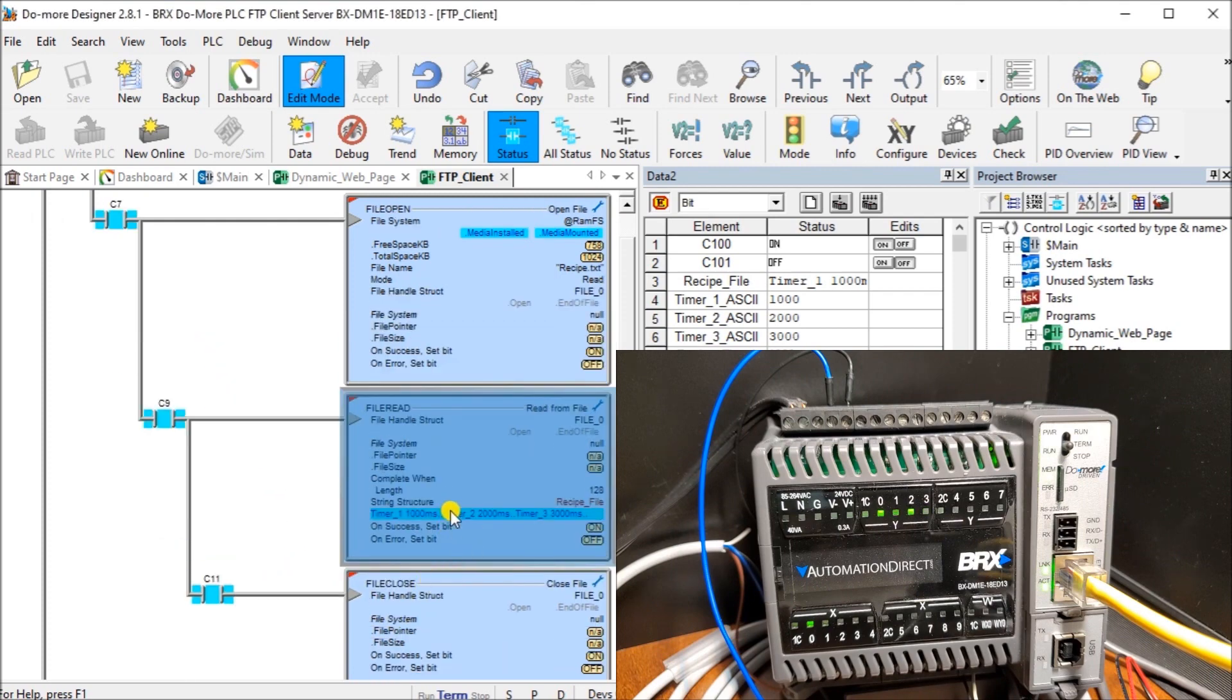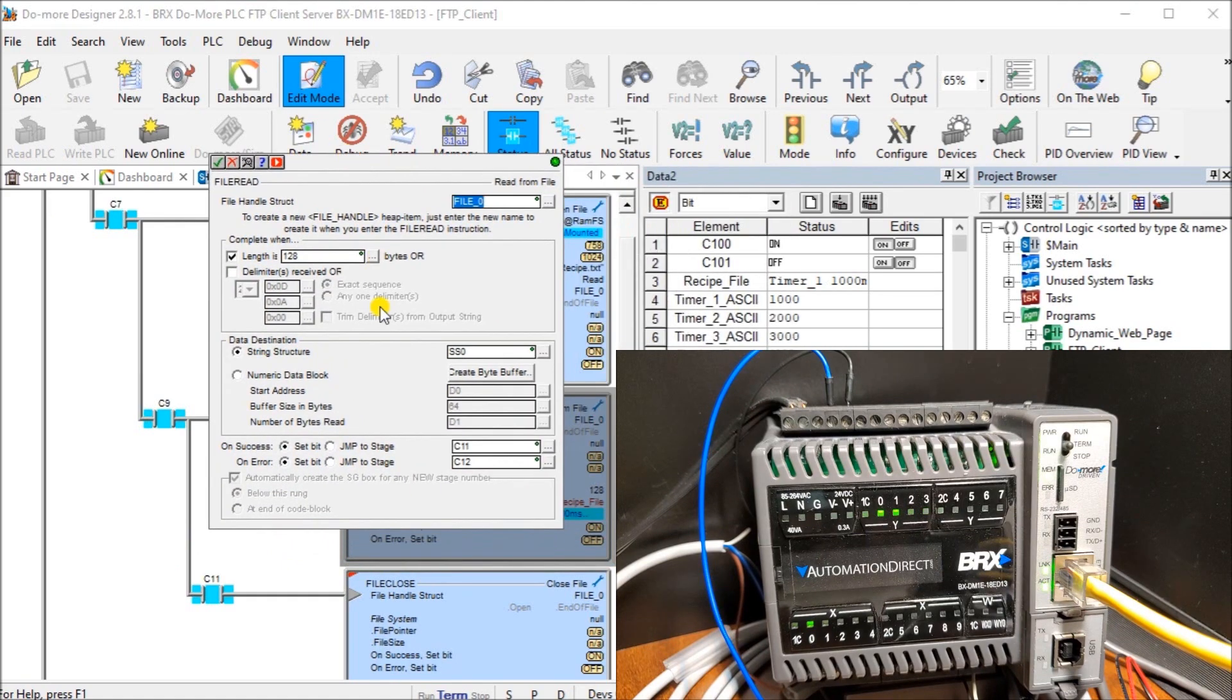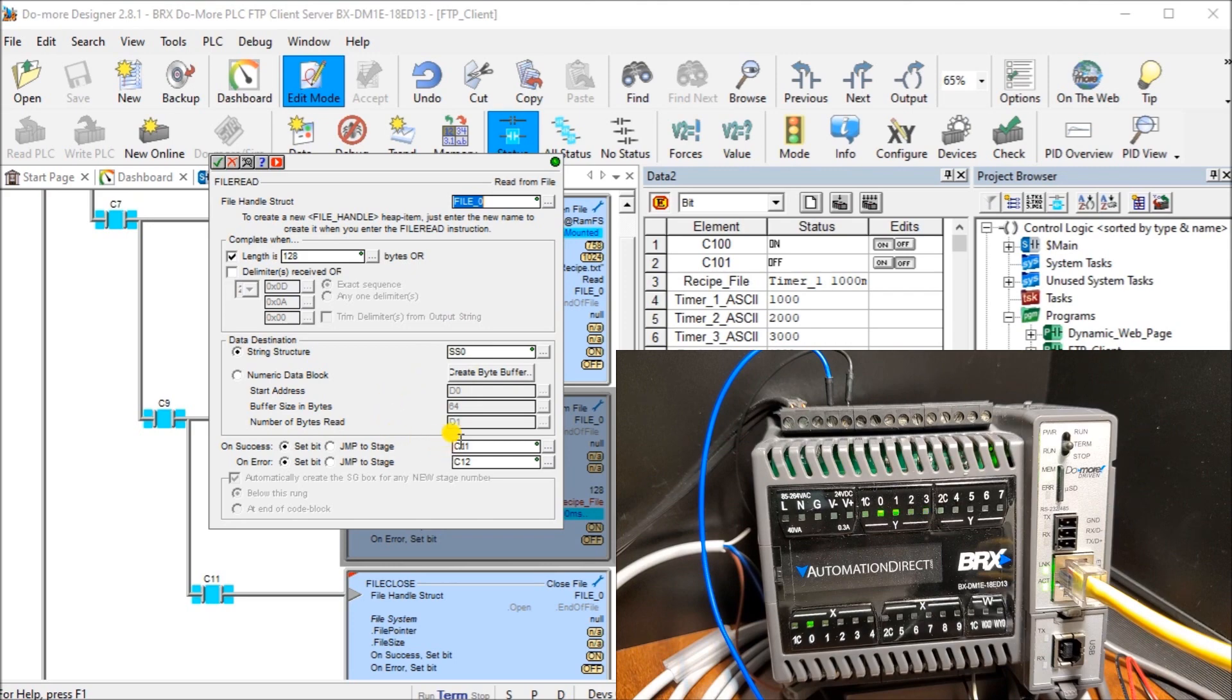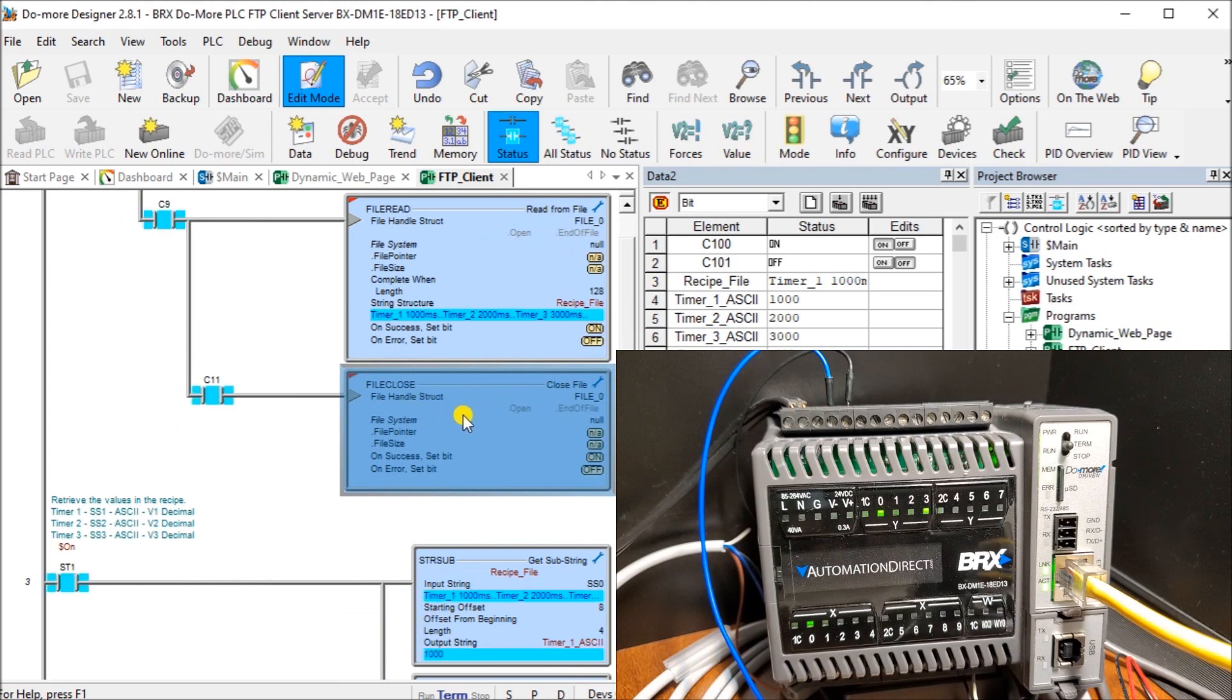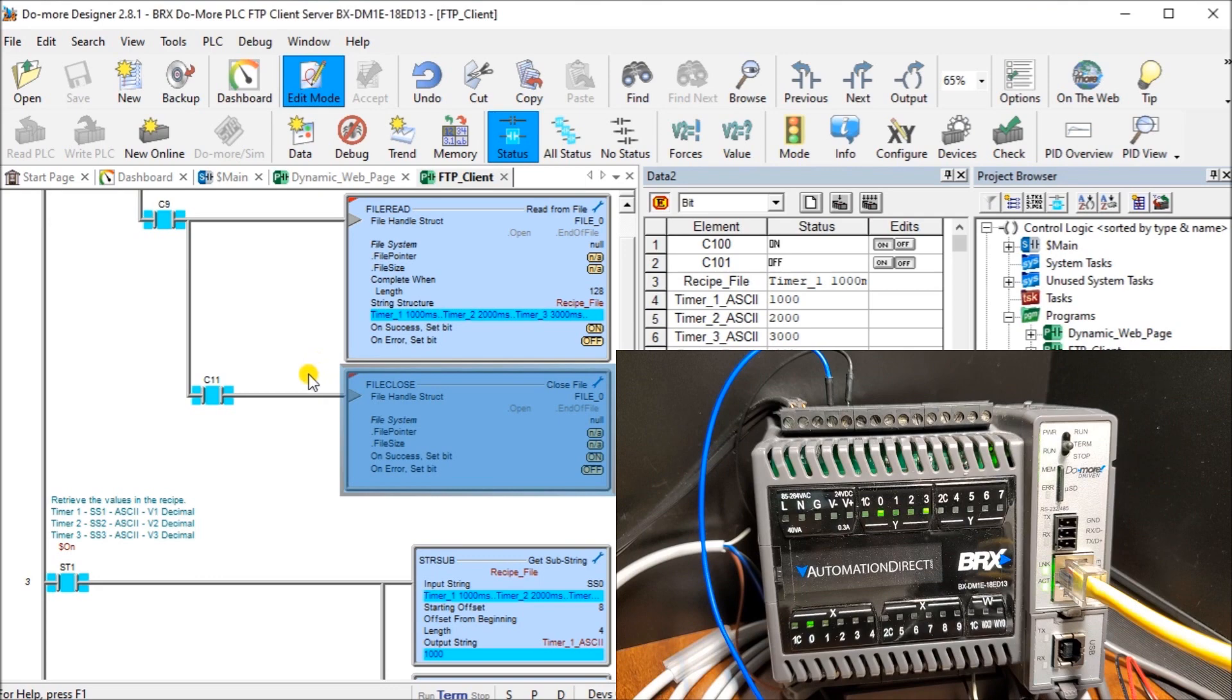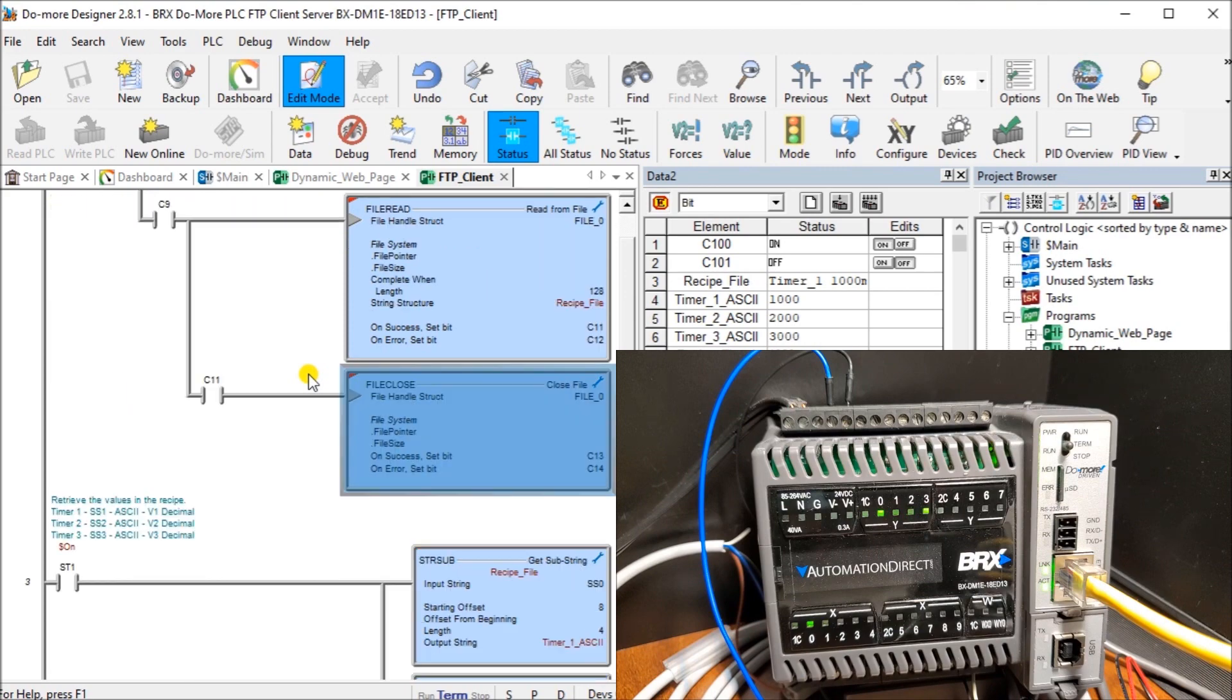Once C9 comes on, we actually do a read file. The read file will read that file into a string structure called SS0. We have a text file, which is ASCII codes. It all comes in through SS0. When that's successful, we turn on C11. Once C11 comes on, we want to close that file down. Once that file is closed, then we're allowed to open it again or do something else. That's basically the sequence. We get the file. Once the file is retrieved, we open it up, we read it into some variables, and then we close that file down.